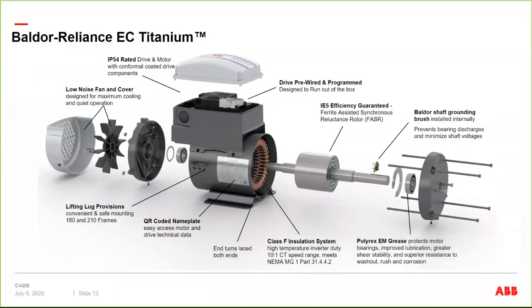And that leads to long insulation system life, less thermal breakdown of grease, allows us to use the totally sealed bearing and give you a long running product. We are using a Mylar nameplate. I'm not going to go into that in a whole lot of detail because I have an expanded section on it, but there's a specific reason we did that because there's a lot more data on the nameplate than a standard metal laser etch type nameplate might have. And all of the product is IP54 rated and passed in test, which I have a slide on and I'll go into. So the standard product is IP54.